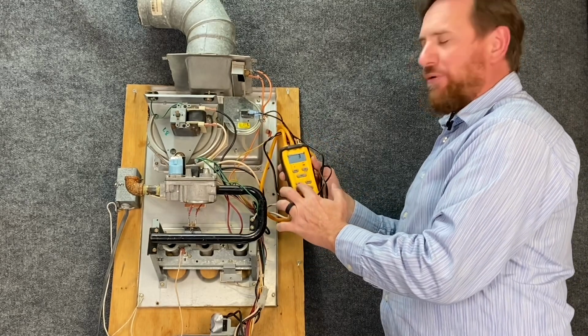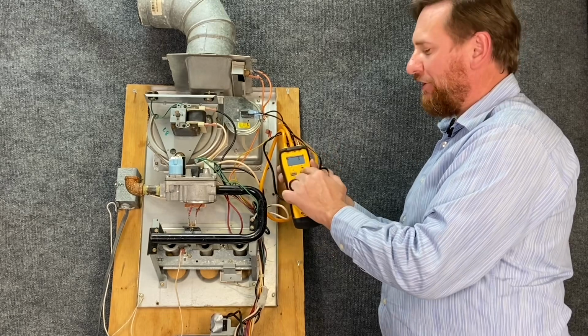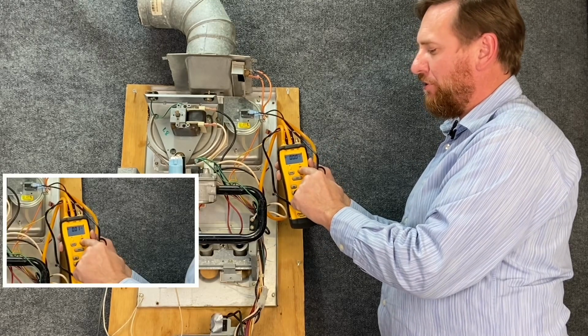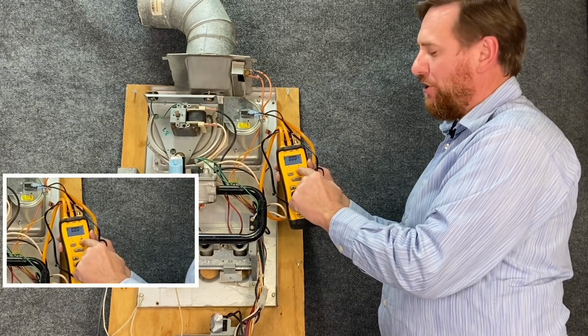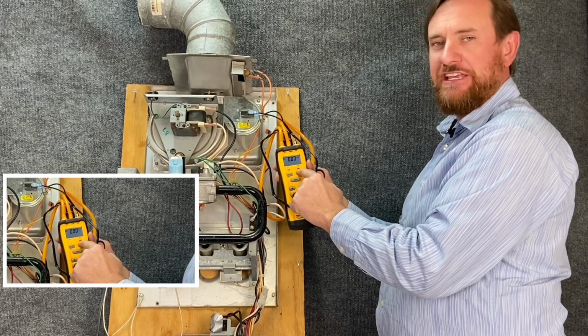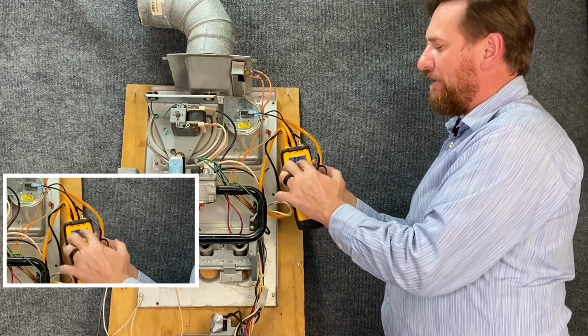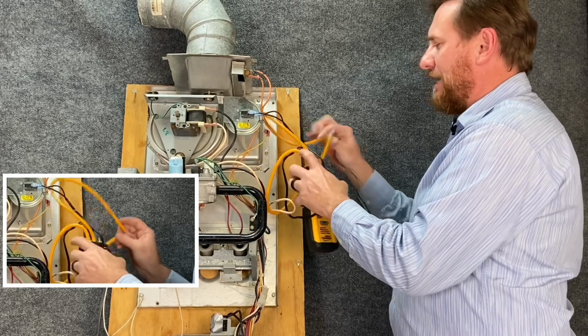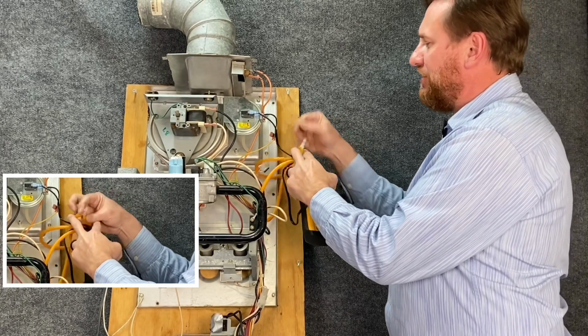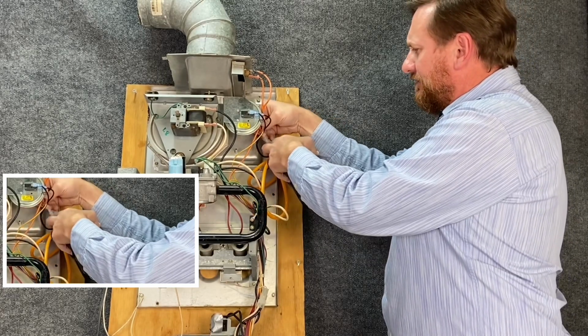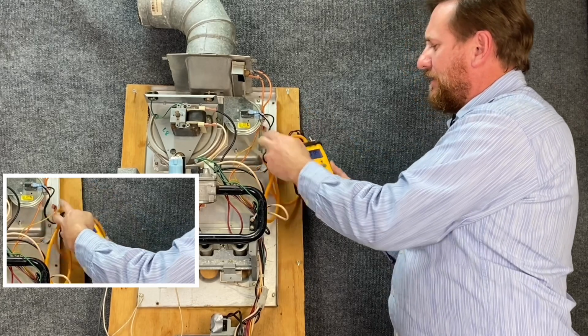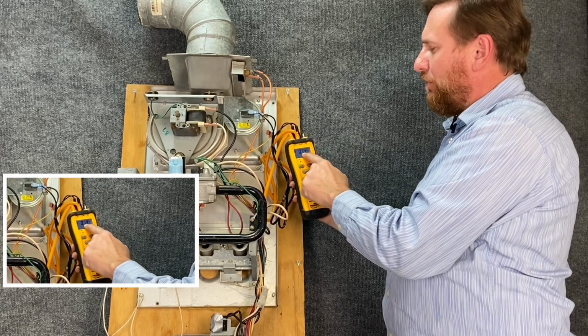I'm going to then increase the pressure until my switch closes. Here there's a little word that says close and a light above it. Once this light goes on, we know that that switch is without a doubt closed. Right now we have 0 inches of water column, and I'm going to plug my pressure switch into this T. So here I have 0.1 inches of water column.